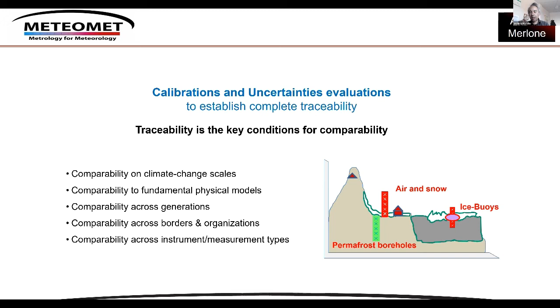Because we need this comparability on the climate change scale, in time, across different fundamental physical models, across generations. Try to imagine if we had fully traceable data in the past. Now the work of climatologists would be much easier. Also across different organizations and nations, or across different instrument and measuring types. I need to compare the temperature in the water of the fjord with the temperature in the ice. How to do that? I need to calibrate, and at some point this calibration needs to be linked to the same something, a standard instrument or reference, whatever it is.